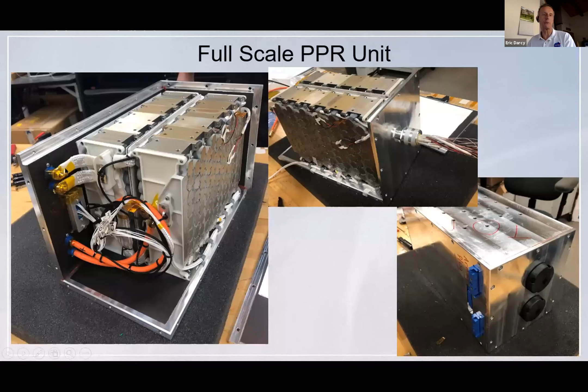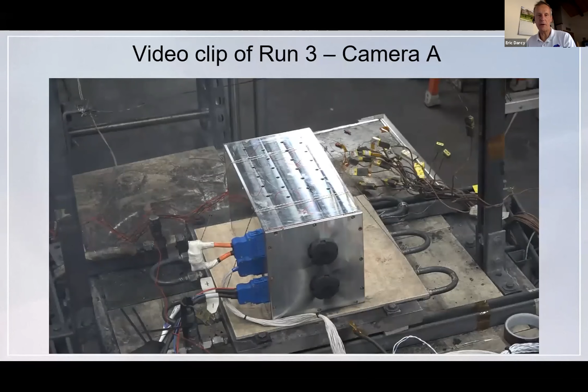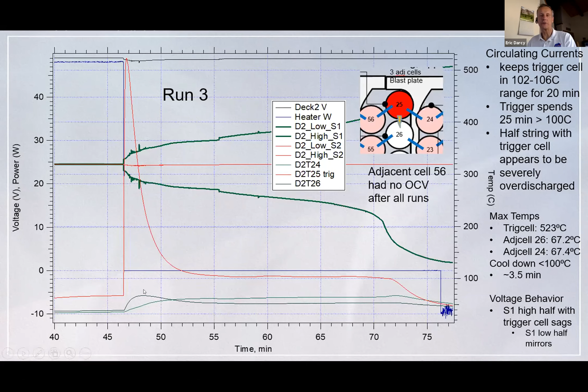And then I've got a video that shows a thermal runaway test of a single cell. And that meets our requirements — a very boring test where only smoke comes out and no flames exit the battery enclosure. The trigger cell gets very hot as expected, but the adjacent cells stayed below 100 degrees Celsius and were very well protected.